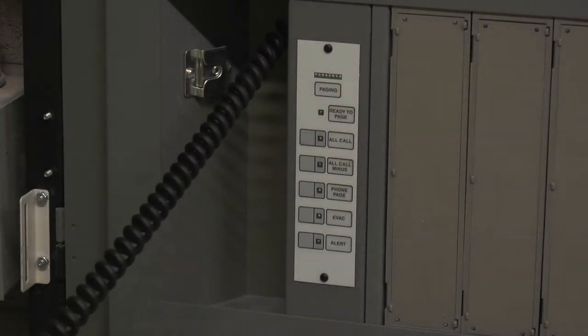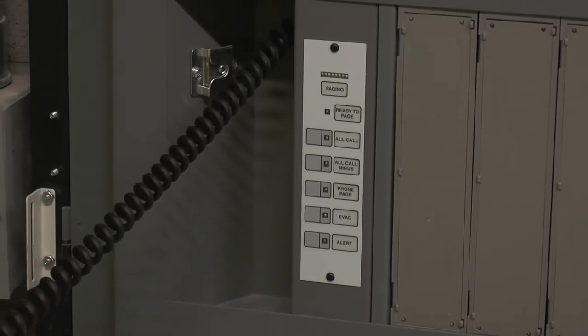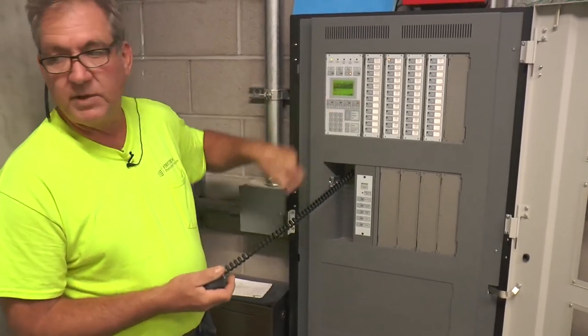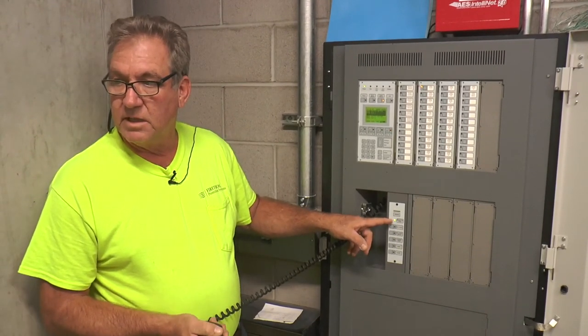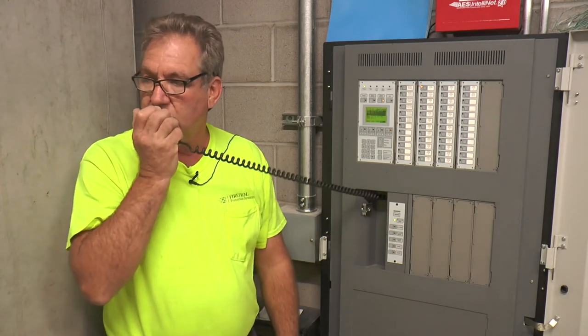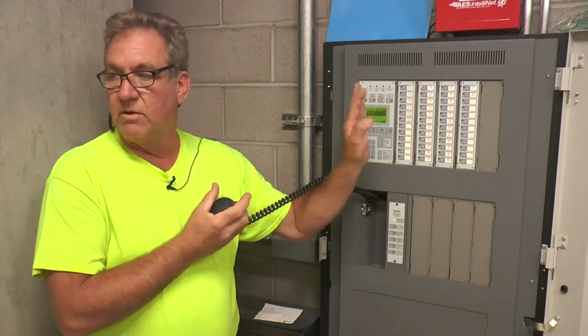What I'll do is page floor one. If I page floor one, I get my page-floor-one-active indicator. I get a pre-tone to get everybody's attention. Now that my light's gone steady: check test, one, two. And you can pick multiple floors.